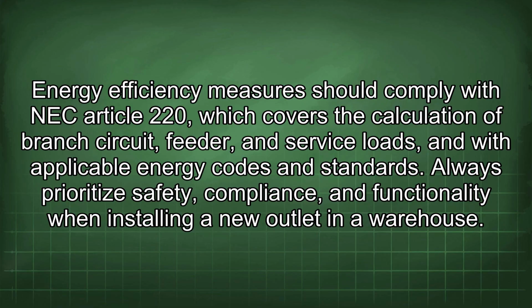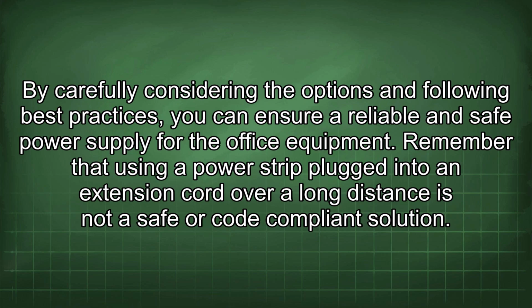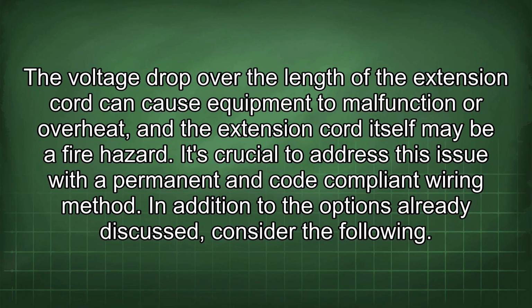Always prioritize safety, compliance, and functionality when installing a new outlet in a warehouse. By carefully considering the options and following best practices, you can ensure a reliable and safe power supply for the office equipment. Remember that using a power strip plugged into an extension cord over a long distance is not a safe or code-compliant solution. The voltage drop over the length of the extension cord can cause equipment to malfunction or overheat, and the extension cord itself may be a fire hazard. It's crucial to address this issue with a permanent and code-compliant wiring method.